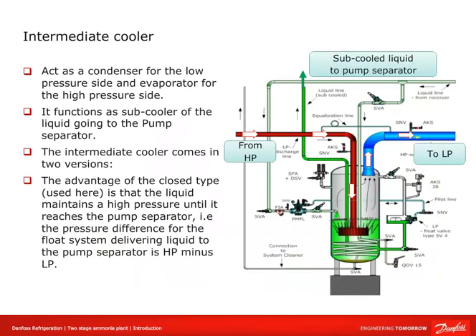The intermediate cooler acts as a condenser for the low-pressure side and as an evaporator for the high-pressure side. It also functions as a sub-cooler of the liquid going to the pump separator. The hot gas coming from the high-pressure side mixes with liquid ammonia and evaporates some of it, meaning the amount of refrigerant going through the suction side of the high-pressure compressor is greater than the amount of ammonia delivered from the low-pressure compressor into the intermediate cooler.